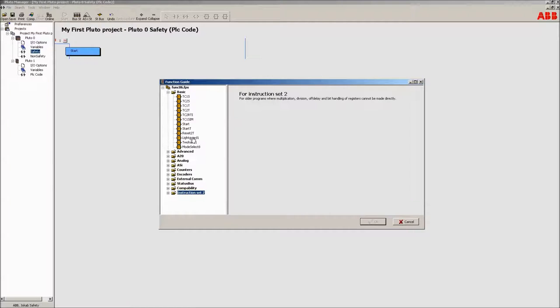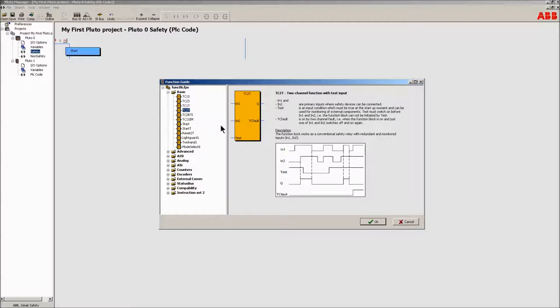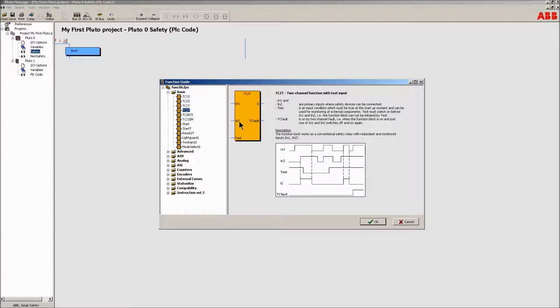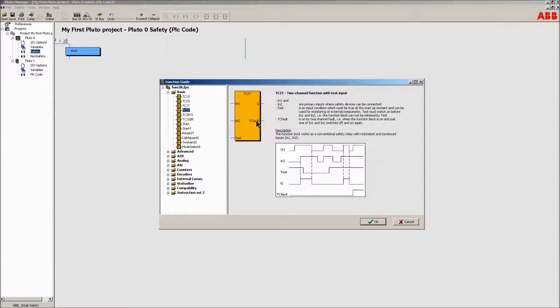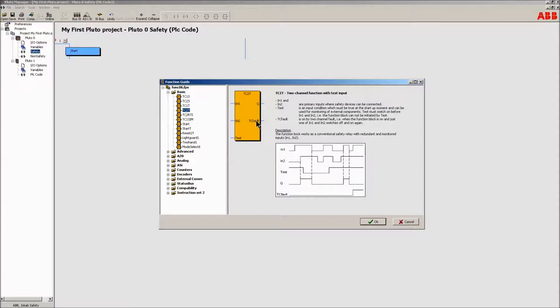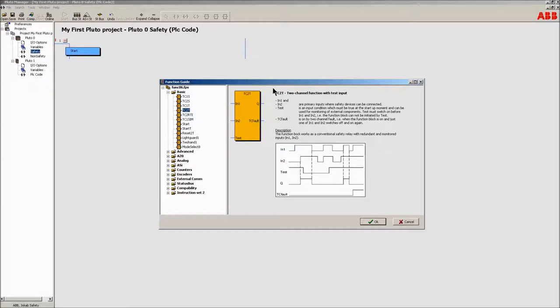The tc2t block will be used to realize the two-channel emergency stop function. This block uses two inputs out of three and performs monitoring of any two-channel faults that may occur. A two-channel fault is when two inputs that are expected to always follow each other only switch one channel off and then back on again, as an example a loose cable causing a poor connection. This is not normal behavior and it must be detected. The block's function is fully described in any of the available languages.